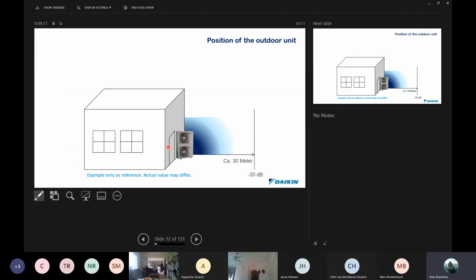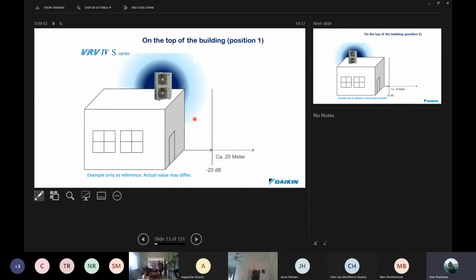Right, so let's go through this and have a look at what we've got. Here's our picture again. This time we're standing back a bit, and we can see this blue gradient moving away, and we can see that the gradient here is in a 90-degree quadrant, and basically the sound is breaking out in that quadrant over there. And about 30 meters back, you're getting about minus 20 decibels. What happens now if we take this unit and we move it to the top of the building, but close to the edge?